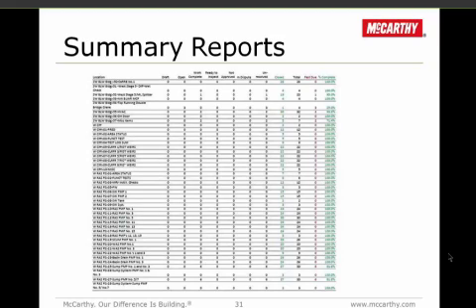What's interesting is when this overall report is printed, you could see that as the startup was going, it went from the motor control to electrical rooms. You could see things reaching 100% sign-off and approval for VFDs, for switchgear, for panel boards. Then we could go out and see the next activities, like is the local control panel wired?